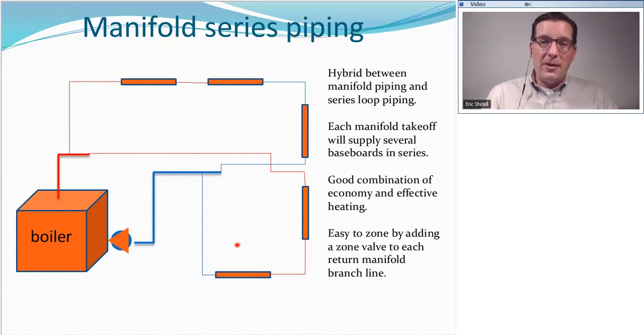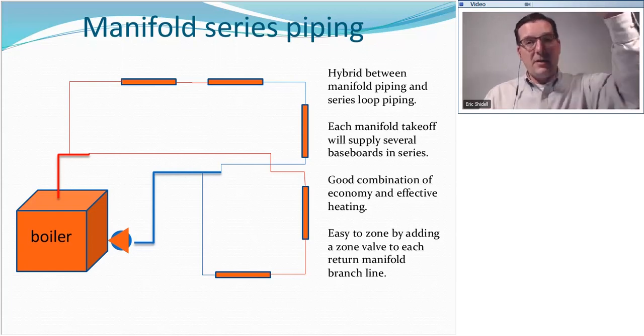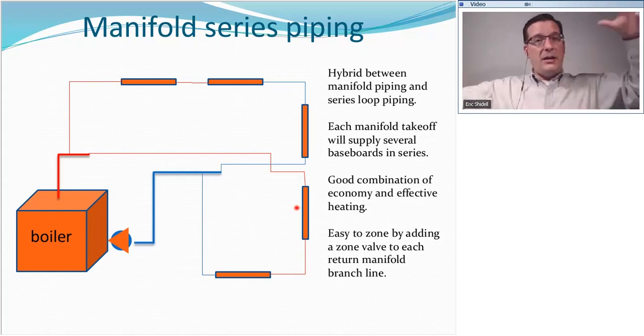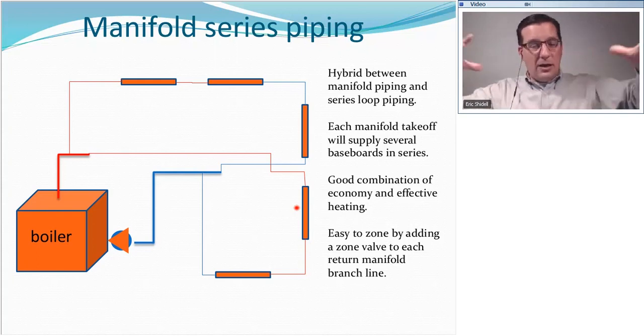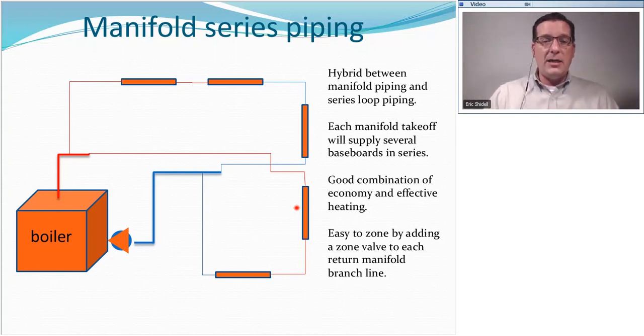This is probably the most common style of piping system in a home that is zoned. For example, you can see we have two distinct zones of heating. Here's one, and here's another. This could be upstairs or downstairs. This could be the east side and the west side, or any combination thereof. It's very easy to zone this into independent zones by controls by putting an automatic valve here and an automatic valve here, and then we deliver the heated water to the zone when needed, stop it from going when it's not needed. Like I said, most common type of system on a zoned residential installation.